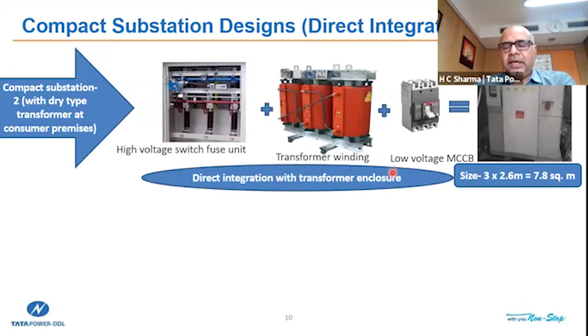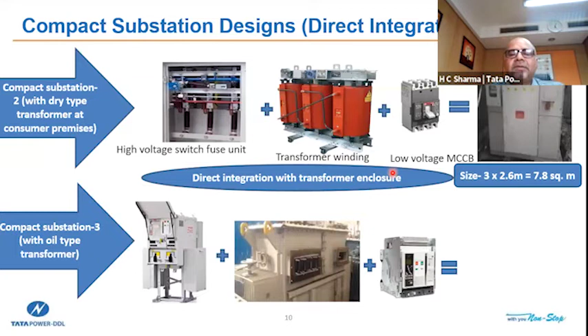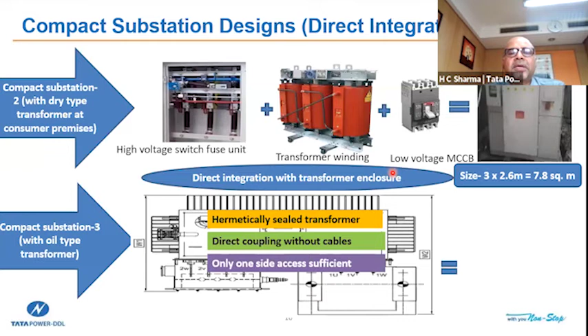Another configuration uses a switch fuse unit, transformer, and LV side MCCB. The earlier system used a dry type transformer; this one uses a normal transformer. Again, the HV and LV switchgears have been combined into one, saving a lot of space. You can even install a few more switchgears or installations in the same available space. These are real pictures of the equipment installed.